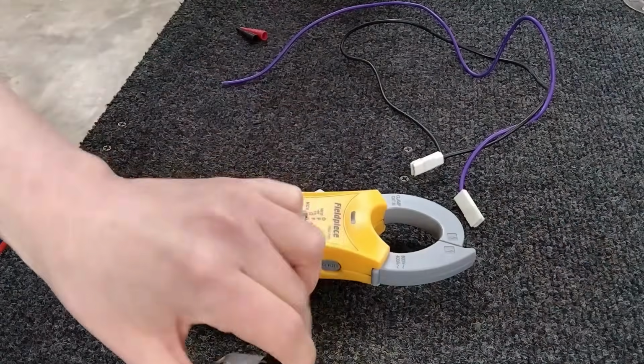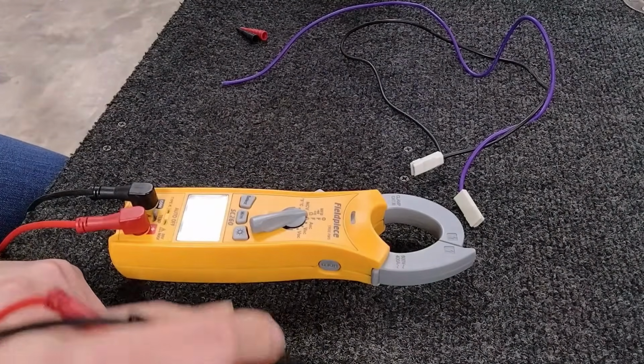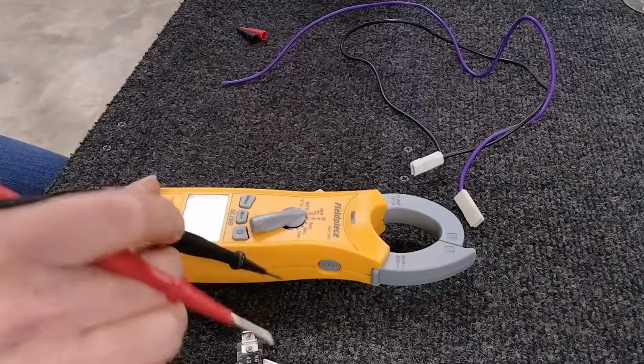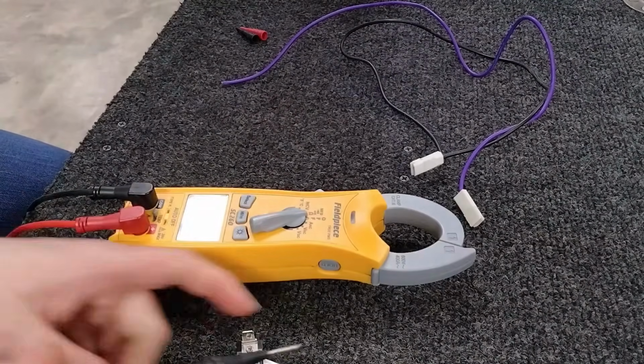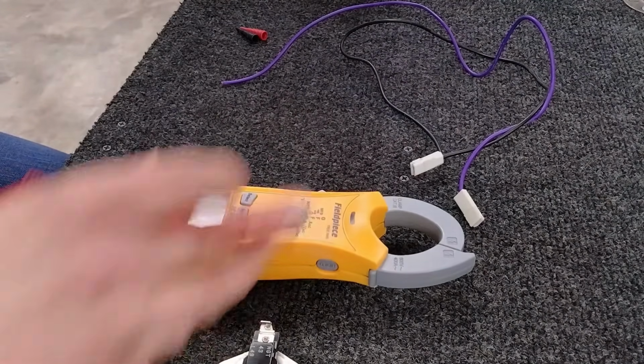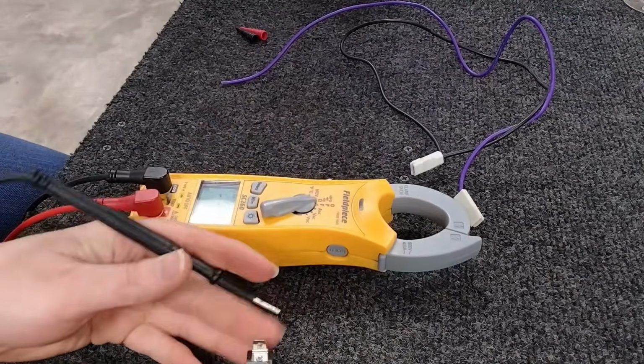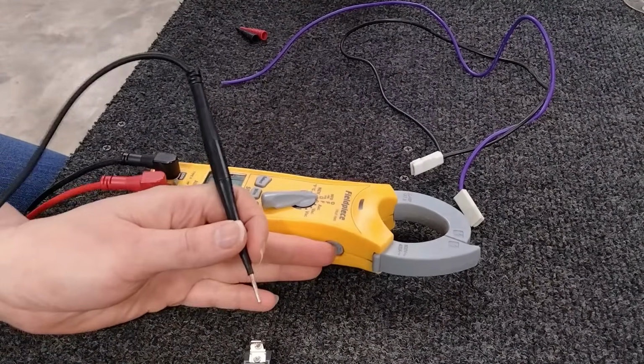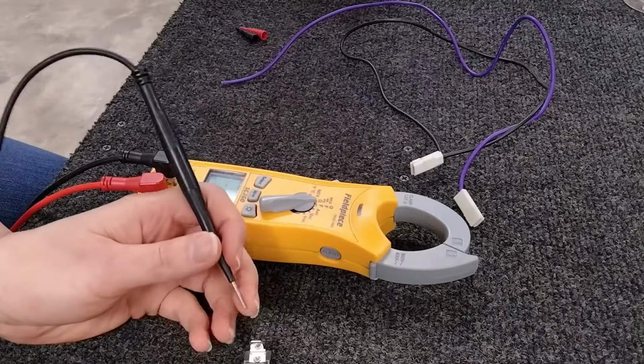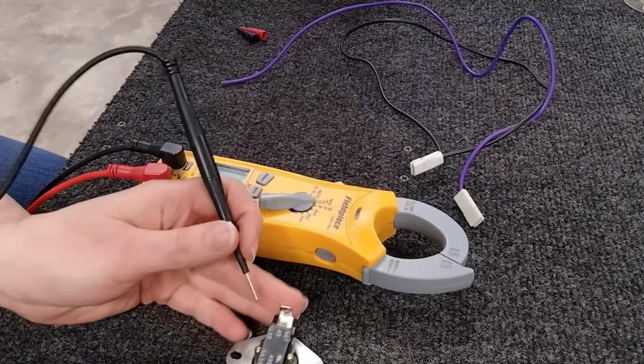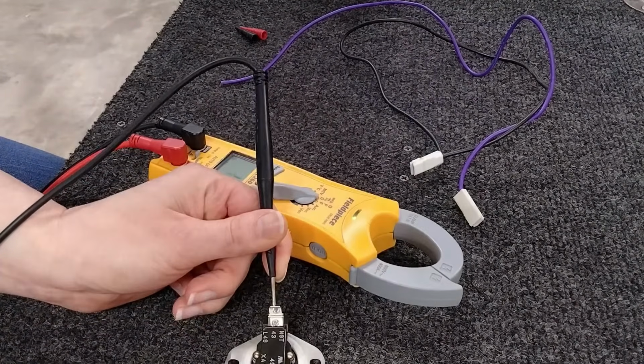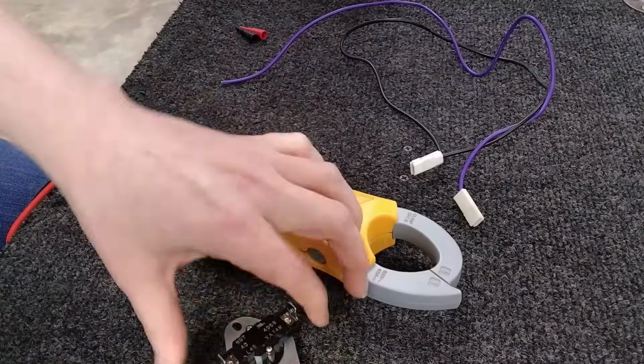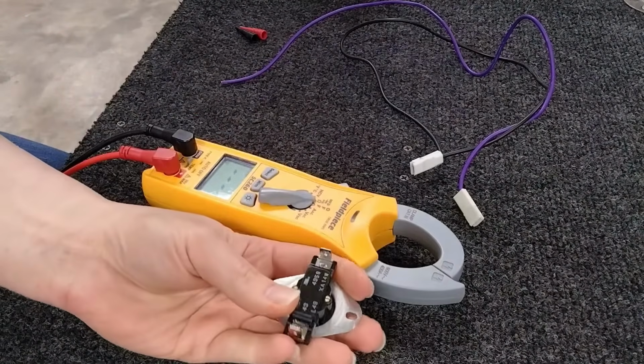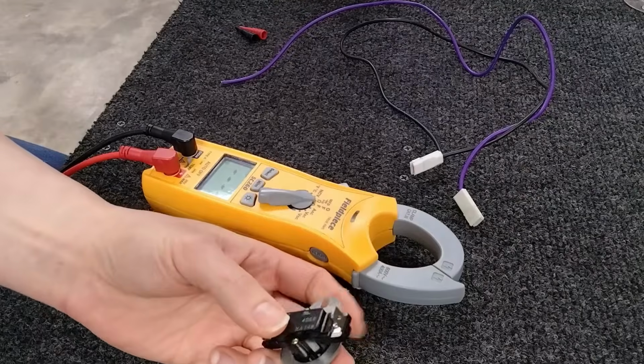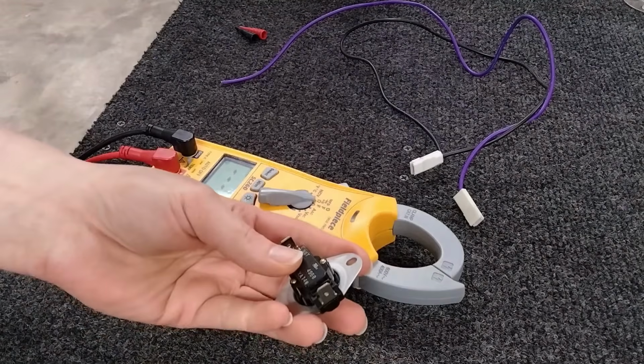Same with these. Every single one of these that go in line to let your furnace know, hey, everything's cool, keep running, they all should be closed. Now there are a few exceptions when you get into air handlers and electric heating and whatnot, but with these, they should always have continuity. So what is a good way to tell when a limit is bad?